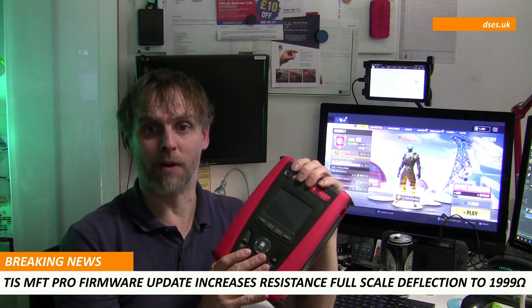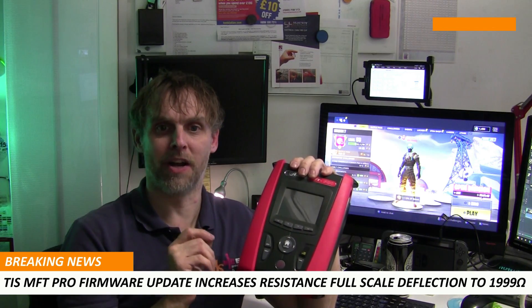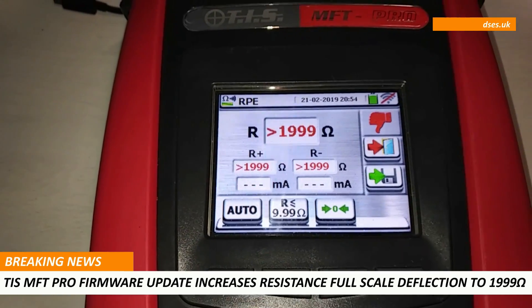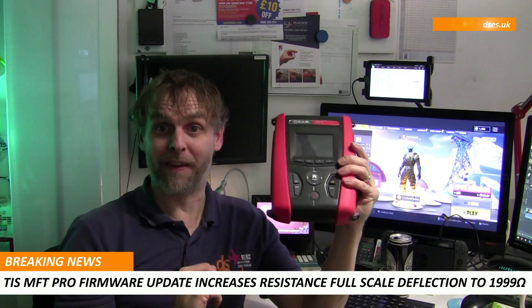Well here's the breaking news: TIS have a firmware update which ups the range to 1,999 ohms, and the rep kindly applied the update for me there and then.